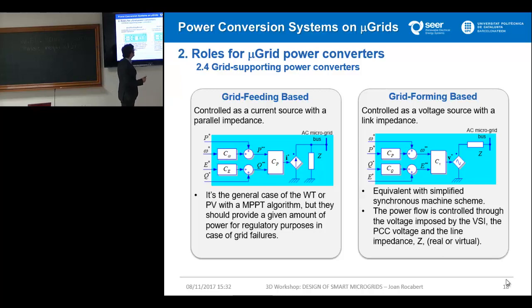Also, this system can be developed from the grid forming converter. What is that idea? It's mainly the same, but instead of a current control source, I'm going to get a voltage control source. In that system, the converter gives the frequency and the amplitude of the grid, and those values are modified according to droop functions between the reference and the P and Q curves coming from a higher level system.